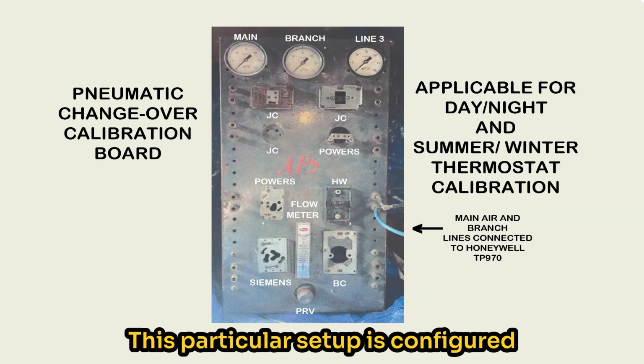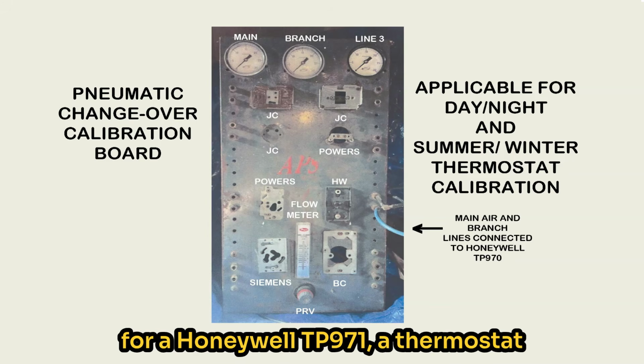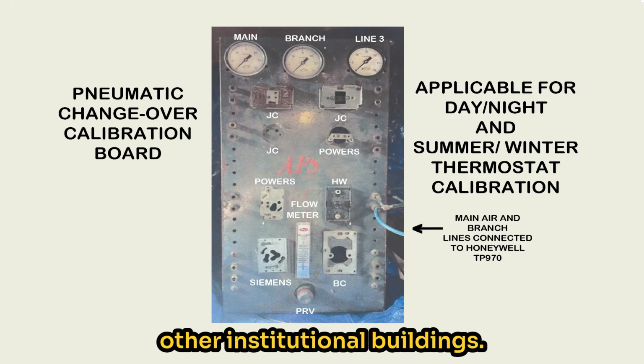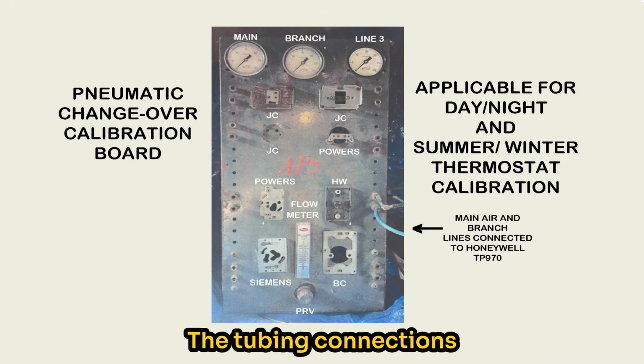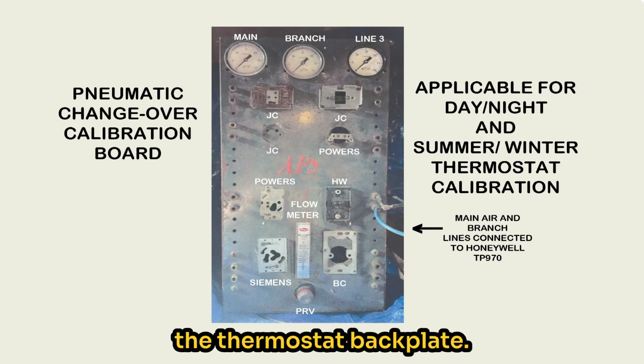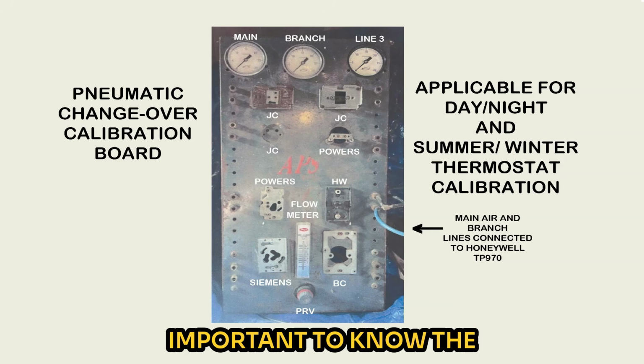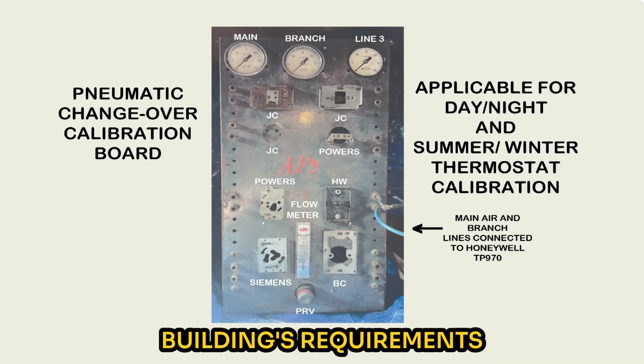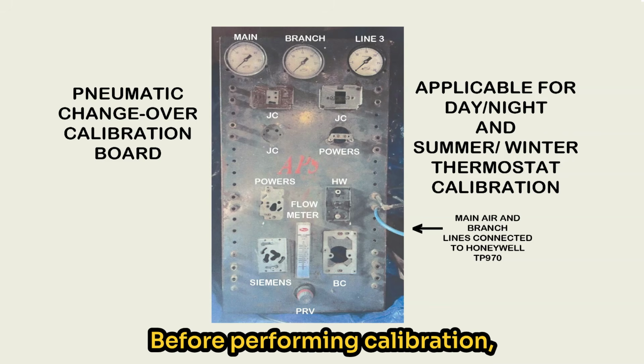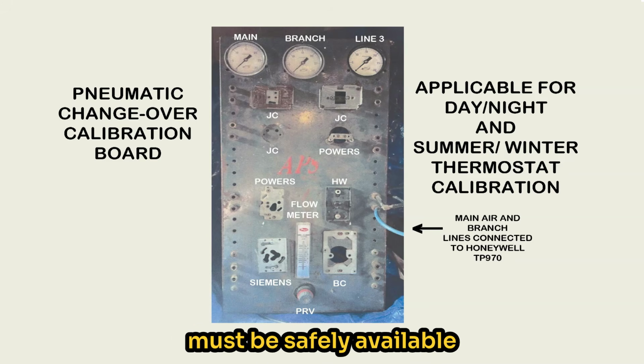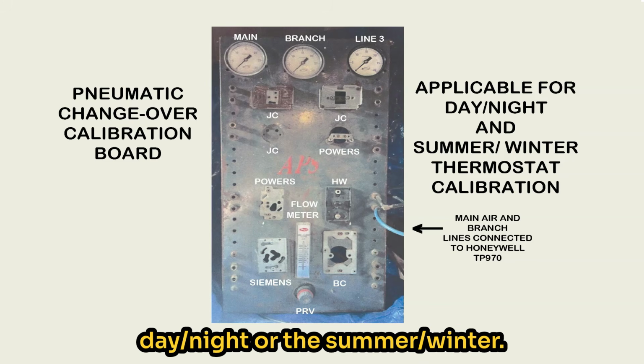This particular setup is configured for a Honeywell TP970, a thermostat commonly found in schools and other institutional buildings. The tubing connections shown are connected to the thermostat backplate. Important to know, the building's requirements. Before performing calibration, the higher mode pressure must be safely available at the calibration board. Do not assume that a particular pressure represents the day-night or the summer-winter.